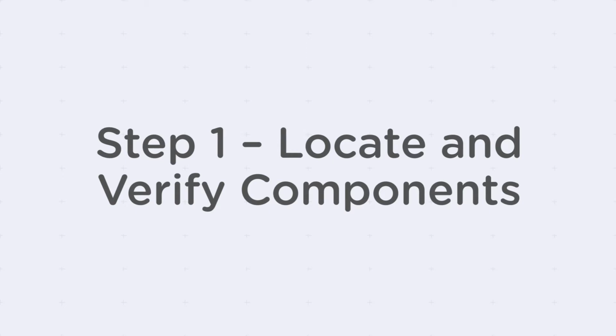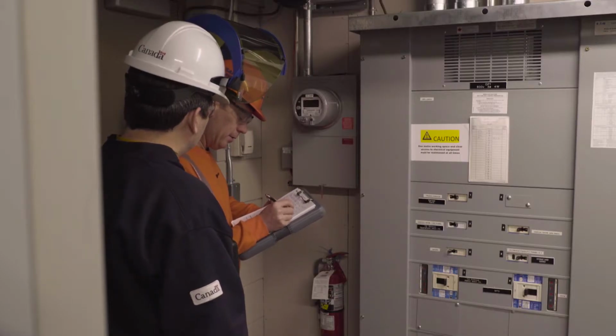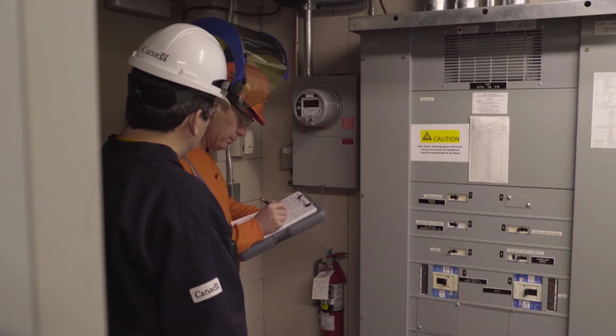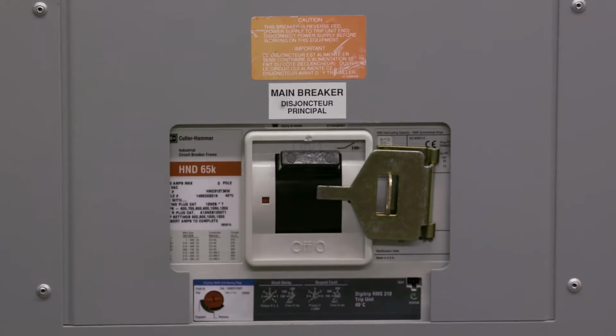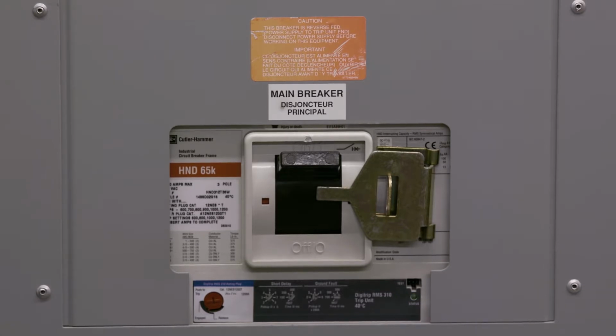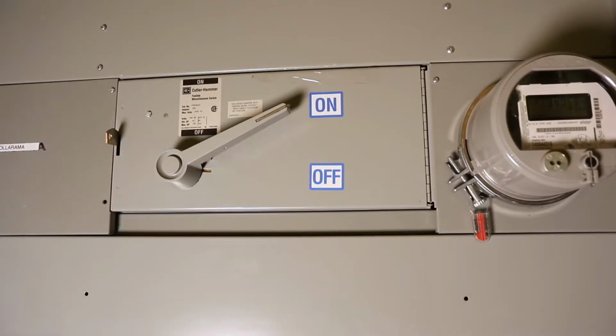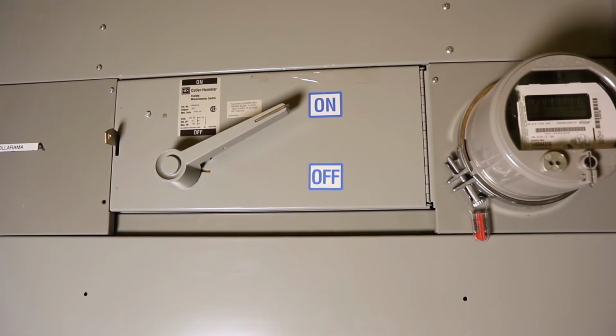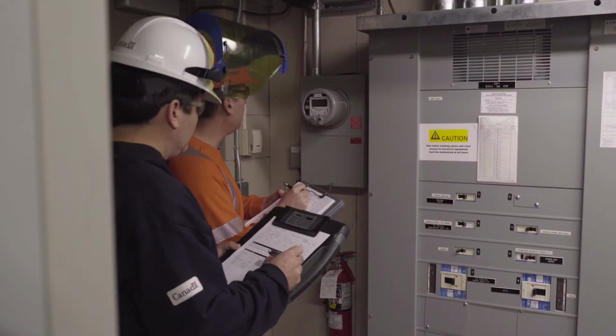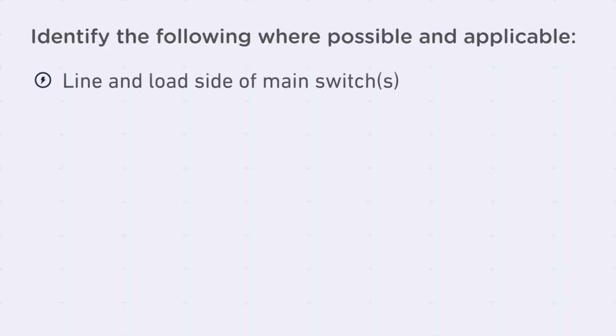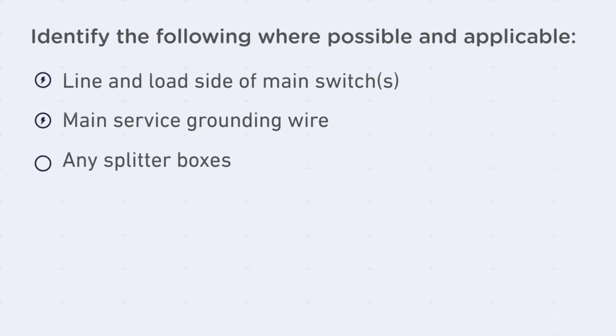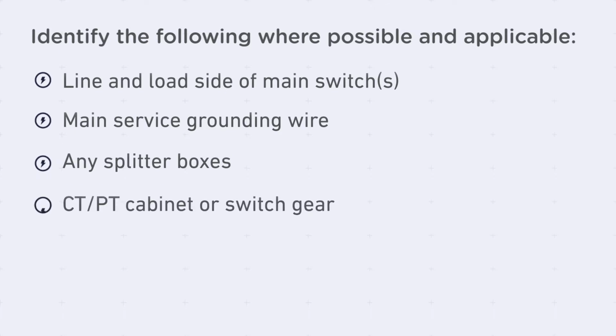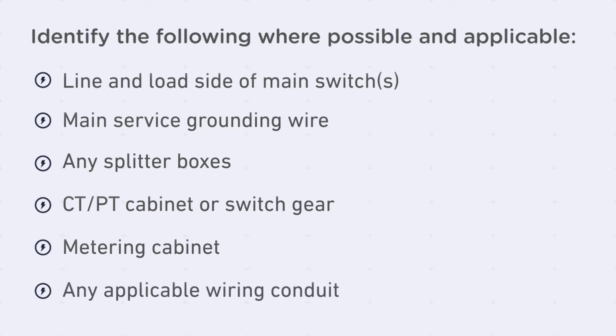First, make sure to locate and identify all components and either record or verify all necessary information of the metering service. A. Locate the main switch of the incoming service, and, if different, also locate the main switch of the service being verified. B. Identify the following where possible and applicable: line and load side of main switch or switches, main service grounding wire, any splitter boxes, CT/PT cabinet or switchgear, metering cabinet, any applicable wiring conduit.